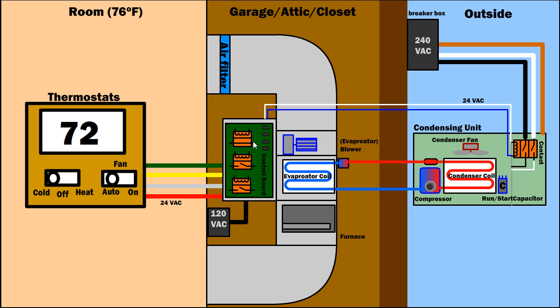We have in the previous steps, I'm assuming that you watched that short video that I had on the bottom and you've realized that your thermostat is working and the wires are working and there's nothing wrong with the controller board. So if all those assumptions are correct, now normally what happens is that I go outside to the condensing unit and I want to check for the 24 volts AC signal.